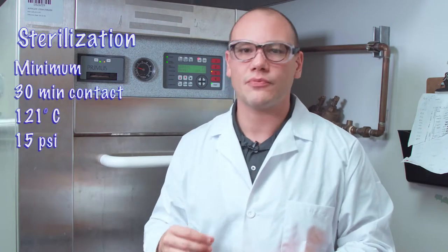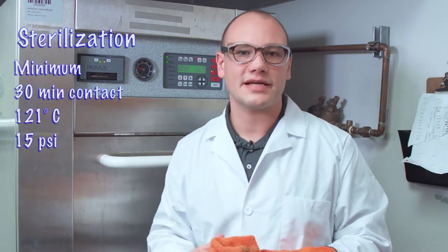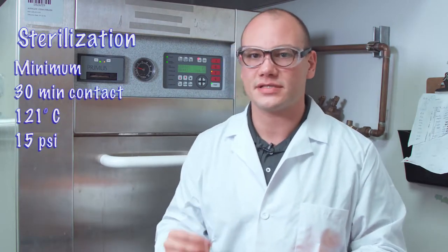Next make sure to select the appropriate cycle for your application. Keep in mind that in order to sterilize materials we need to employ a minimum of 30 minute contact time at 121 degrees Celsius and 15 psi.